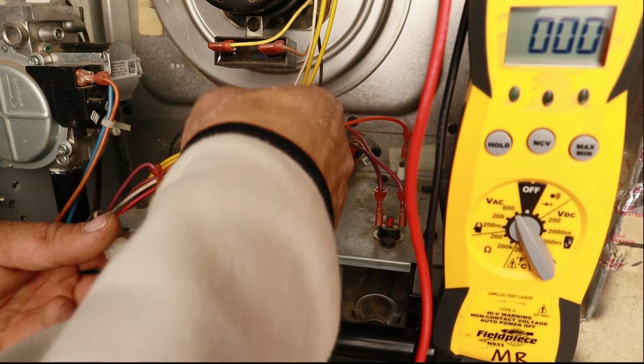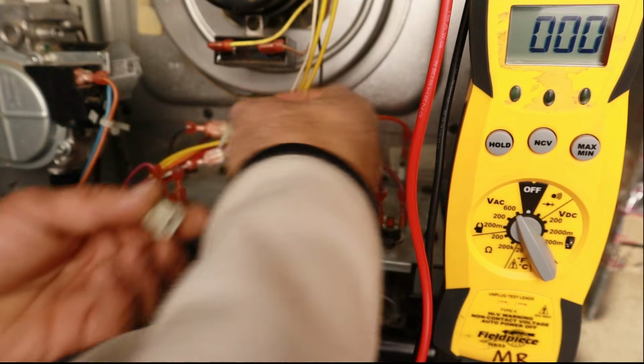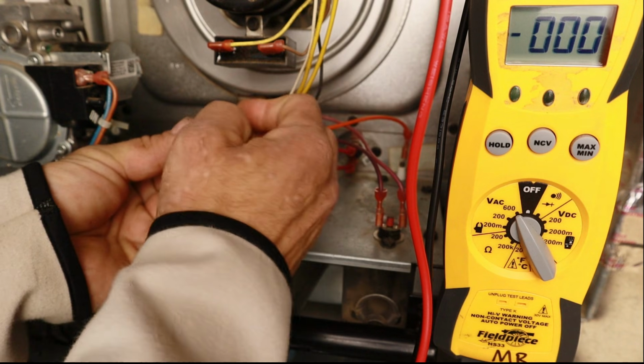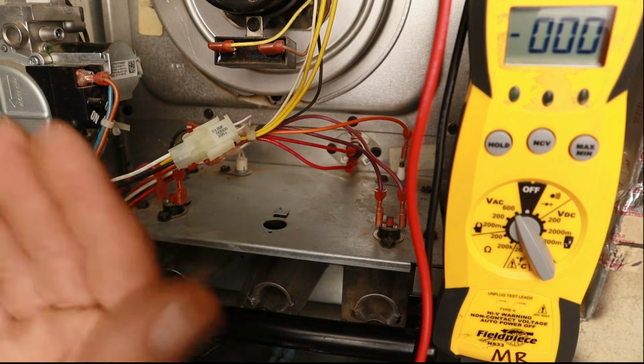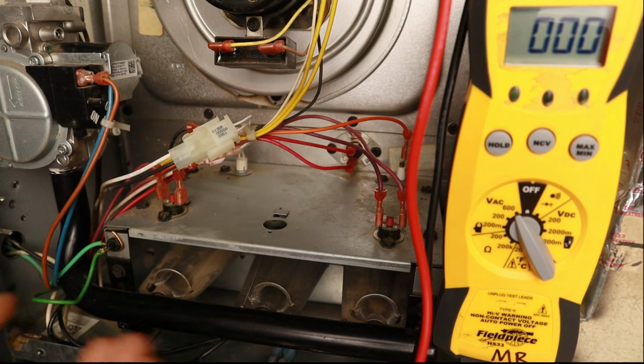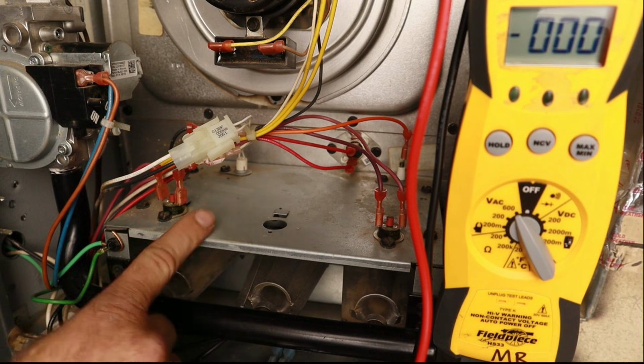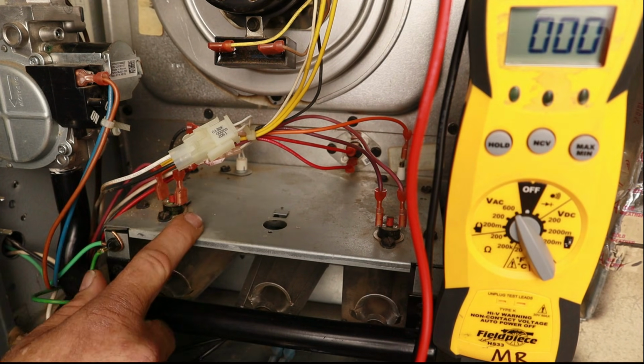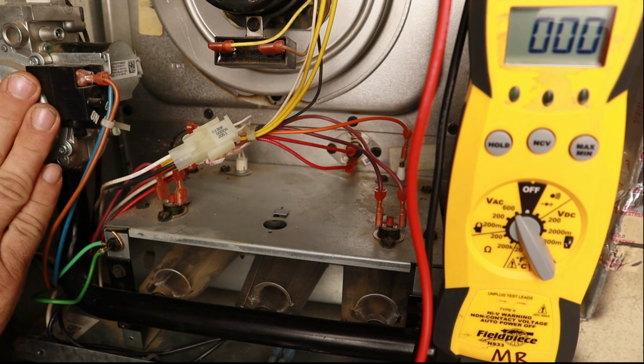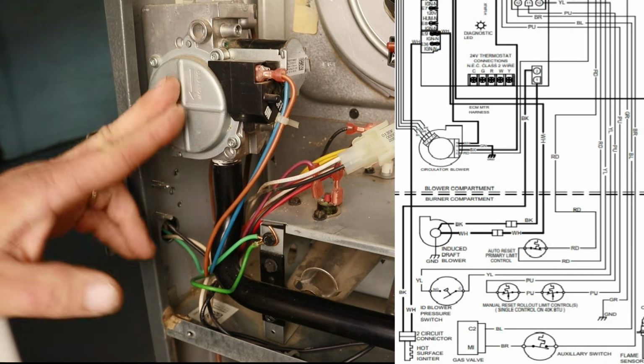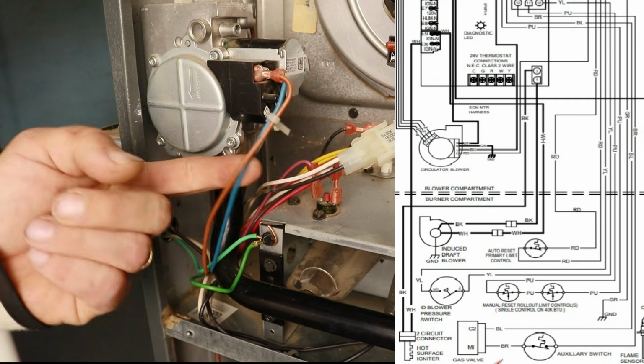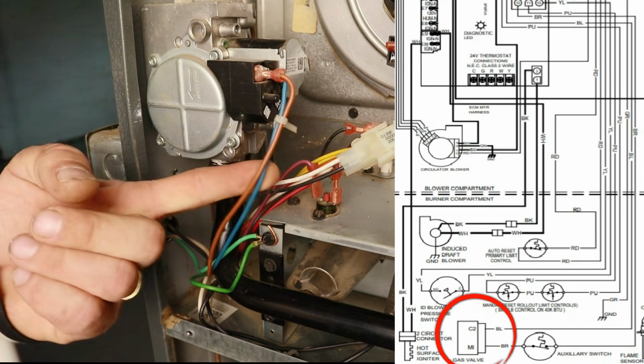So let's go ahead and plug this back in, shut the power off. We'll plug this back in and then we will restart this and allow it to go through its sequence all over again. Now once the hot surface igniter begins to glow, the next step is for our gas valve itself to open. So here's our gas valve. We look at the schematic, we see we have a blue and a brown wire coming to this gas valve.